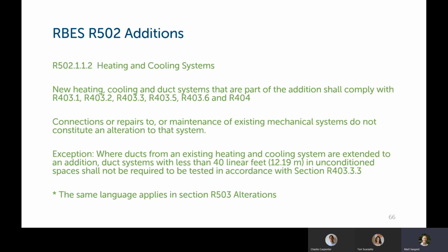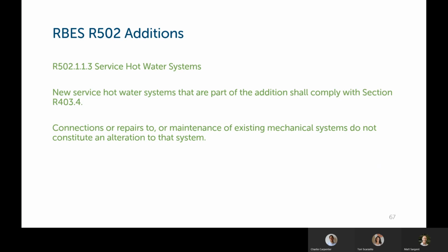There's an exception where ducts from an existing heating or cooling system are extended to an addition. The ducts with less than 40 linear feet in an unconditioned space are not required to be tested. They are required to be sealed and insulated as per the code, but they don't need to be tested. And this same language for the heating and cooling systems applies in R503, which talks about alterations to a building. So it's the same whether it's an addition or an alteration. And new service hot water systems that are part of the additions shall comply with the new code. And again, connections or repairs to an existing system don't need to comply with the code.